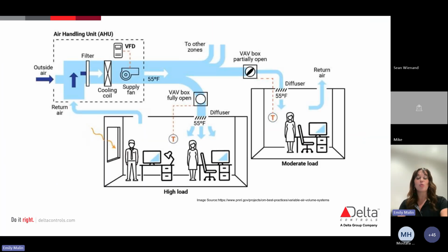So the way that this looks in real life, so that it's maybe a little bit better than our crude rudimentary drawing there, it's going to be 2 different zones. It's the exact same thing that we just looked at. So we have our zone there on the bottom left, which might be a high load zone, right? So what we're seeing there, there's a lot of people in there. Maybe they're having a party. Our gent there has his open window on a hot day. So we're getting our temperature maybe too high, right? We want to continue and maintain that temperature in that zone at 55 degrees, but man, oh man, it's just getting too hot in there.